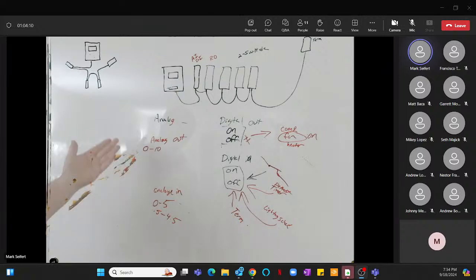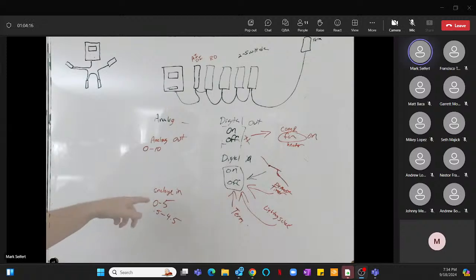As we know, you can control something really well, like just say for instance the analog ins for the liquid levels, they're 1 to 2 volts. But it can go from 0 to 100 in that 1 to 2 volts because it's got decimal points. So it's an infinite range that we have. You can control a condenser drive on 1 to 2 volts because in between the 1 to 2 volts you've got 1.1, 1.2, 1.3, 1.4. You could tell it, hey, it's a 1 to 2 volt, and it'll do its own calculations and it'll run fine, just like it's a 0 to 10.